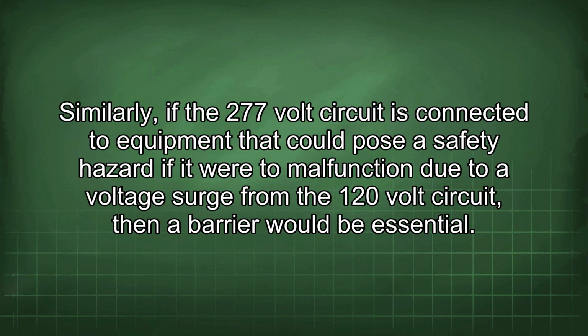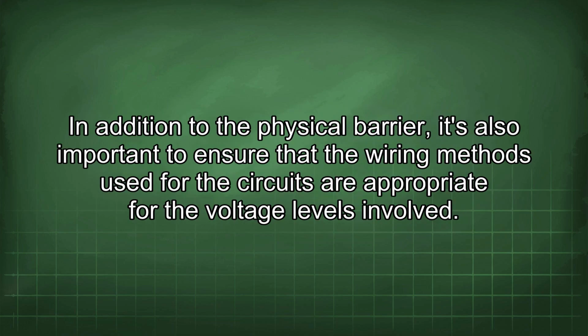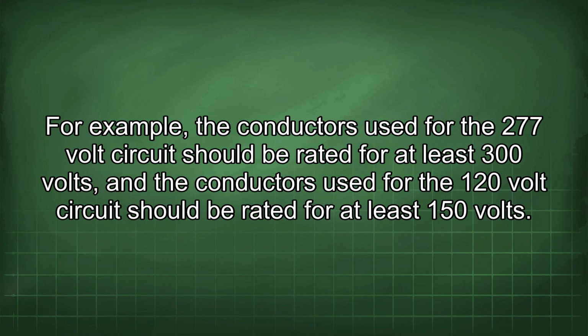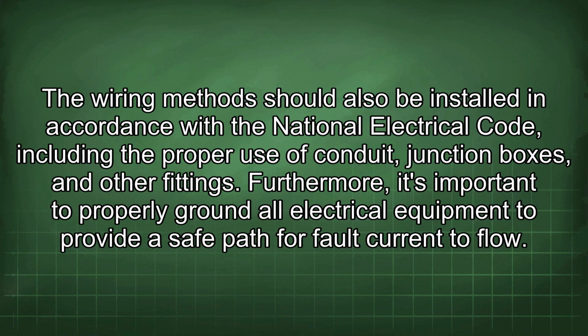Similarly, if the 277-volt circuit is connected to equipment that could pose a safety hazard if it were to malfunction due to a voltage surge from the 120-volt circuit, then a barrier would be essential. In addition to the physical barrier, it's also important to ensure that the wiring methods used for the circuits are appropriate for the voltage levels involved. For example, the conductors used for the 277-volt circuit should be rated for at least 300 volts, and the conductors used for the 120-volt circuit should be rated for at least 150 volts. The wiring method should also be installed in accordance with the National Electrical Code, including the proper use of conduit, junction boxes, and other fittings.